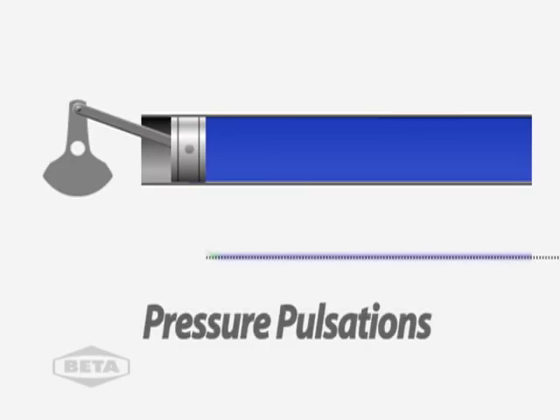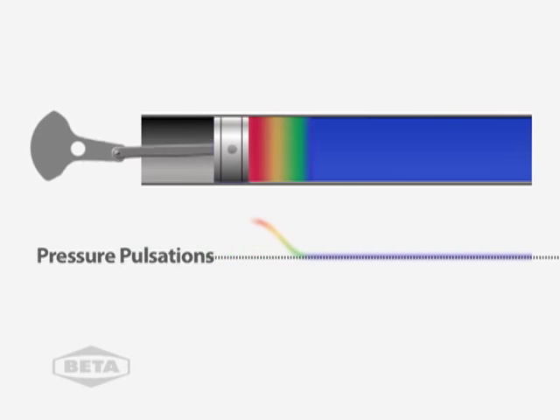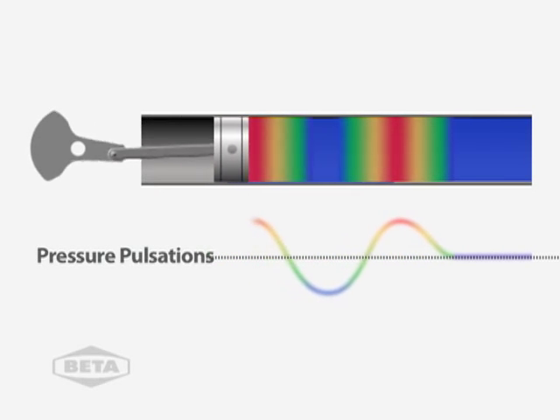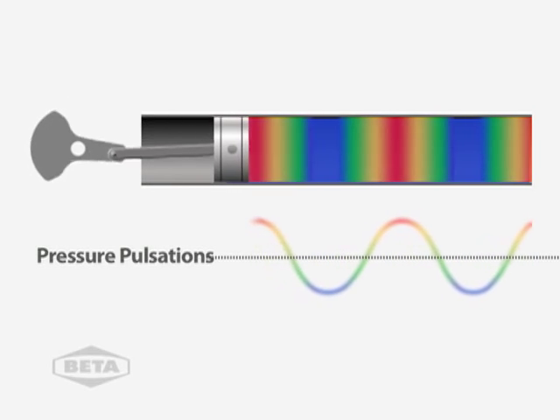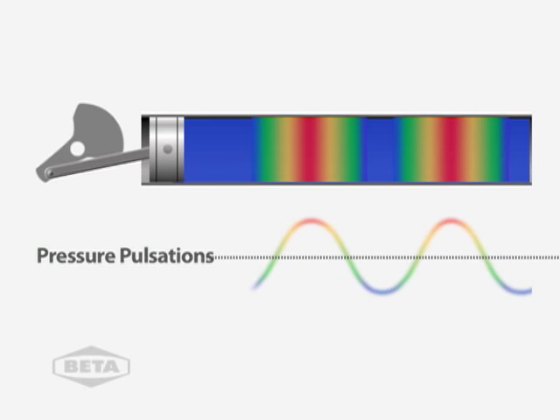Pressure pulsations are created as gas enters or leaves a cylinder in short bursts. Pressure pulsations travel through the piping and vessels. Pressure can create very high unbalanced forces between 10 and 10,000 pounds peak to peak.